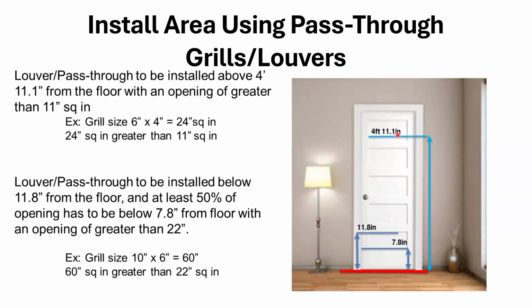Above the 4 foot 11-inch level from the floor, based on this calculation, we would need an opening of greater than 11 square inches. For this example, 6 by 4 would give us 24 square inches. 24 is greater than 11, so that would be acceptable if we put that above 4 foot 11, which I would put up here, rather than cut into the door.